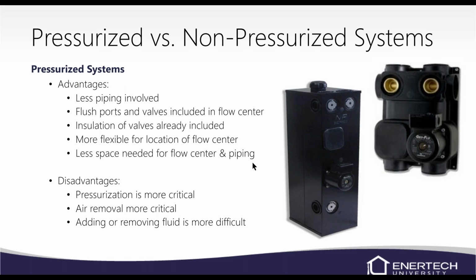Adding or removing fluid is more difficult in the pressurized. Obviously, with the non-pressurized, you can see the canister there. You can take the lid off or the cap off and just look down in there and see what the level is. You can also get a sample of fluid pretty easily. The pressurized, you got to use a PT needle and probably put some pressure on when you're pulling pressure out. So it can be a little bit more difficult. It's not impossible or anything like that. You just have to make sure you got the right tools with you.